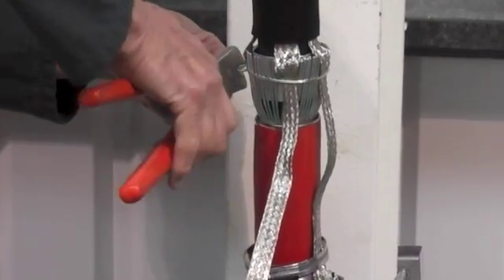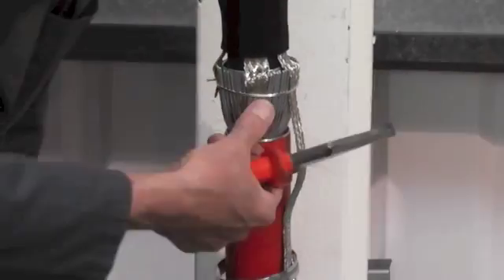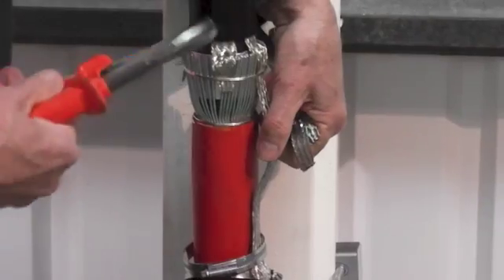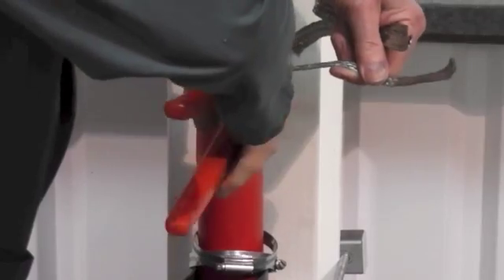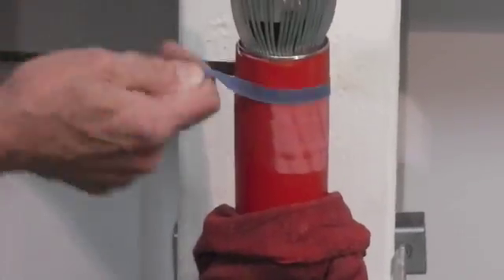Heat the skirt first, and then the fingers to the cores. And if you position the earth kit that you fitted previously correctly, you'll note that the springs are above the end of the fingers. Now those earth braids will be secured temporarily to the armors beneath, as we're fitting an outdoor armor earth kit. And you'll probably need to trim those braids as shown.